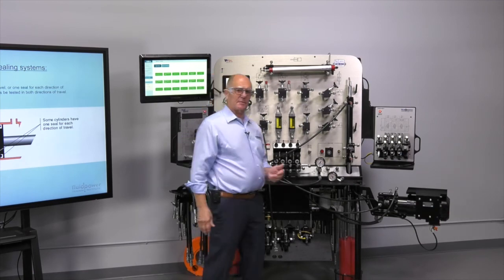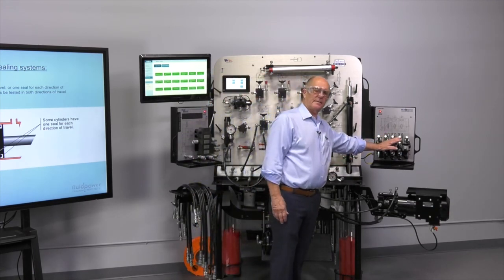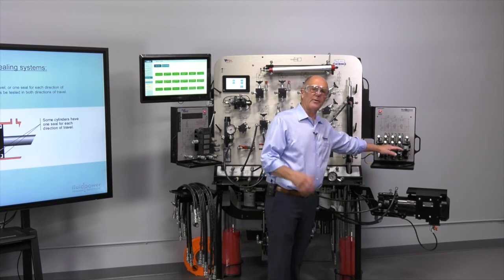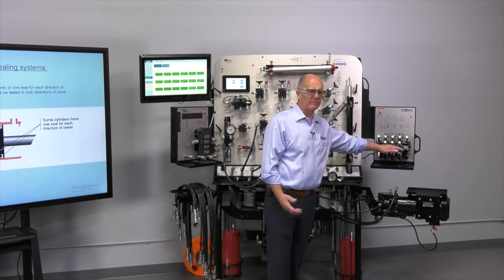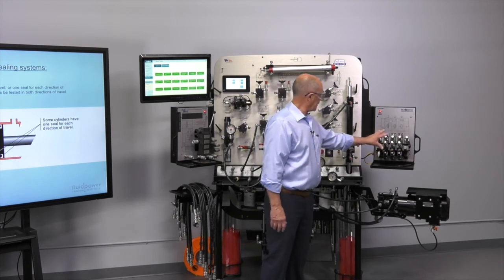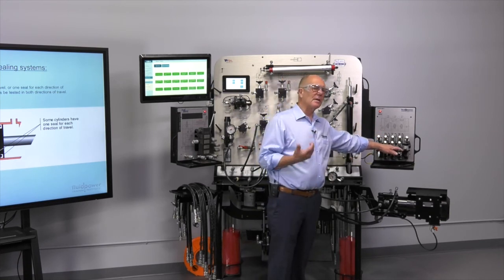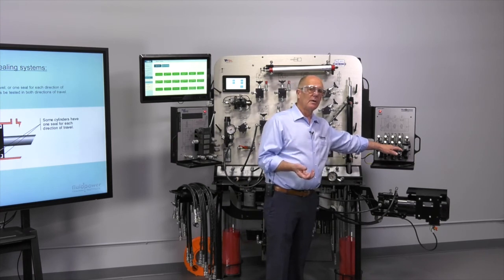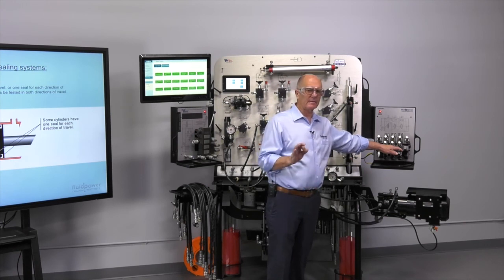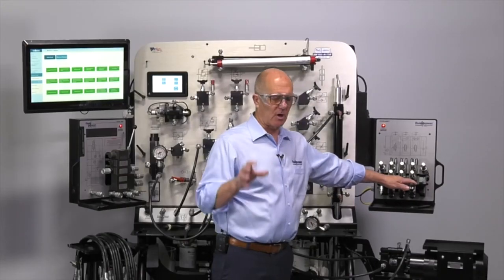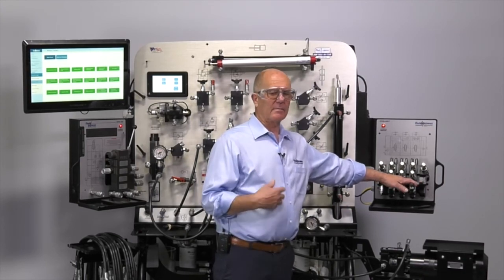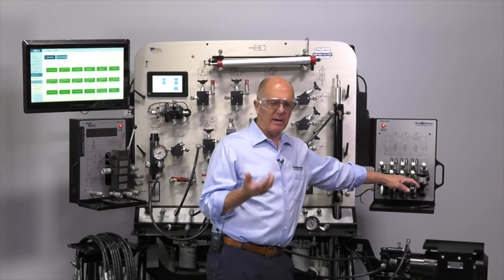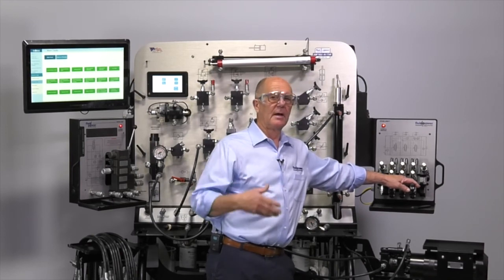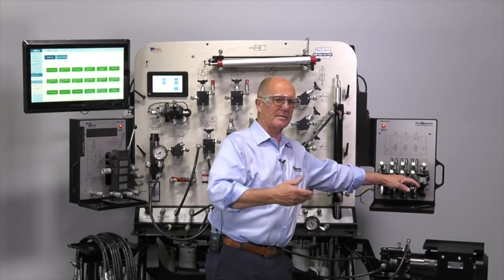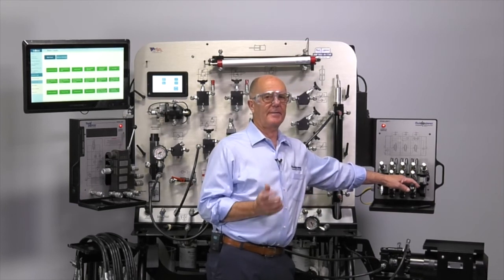What about this? I spoke about the directional control valve here. There's 22 valves in here. They're all within 3 inches of each other. If I put a thermal image on here, I'm going to get heat. But where's it coming from? Is it the spool or bore? Is it the cartridge? Is it the seal? Where's it coming from? You see, there's the problem with heat. You can't find the problem. You can't pinpoint the leakage path. If I trended and I knew the system, I'd use heat as a guide. Maybe I'd start testing there, but I would never assume that that's the problem.